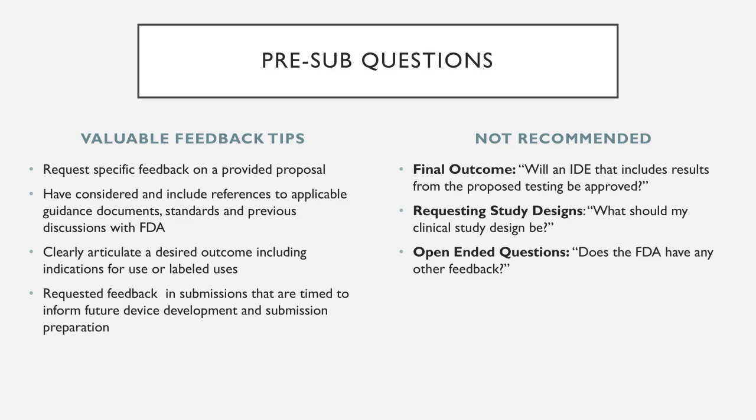Now, the guidance document to the pre-sub process or the Q submission process that the FDA undergoes provides a pretty rich list of not recommended questions or poor quality feedback requests that aren't going to get much back and forth with the FDA. So, any kind of questions that pertain to trying to get the FDA to commit to the outcomes of an IDE or approval request are likely not going to get much on the end from the FDA. So, for instance, if you were to say, hey, will an IDE that includes results from the proposed testing be approved? You're not going to get the FDA to come in and say, yes, we will approve that and have something in such rigid terms.